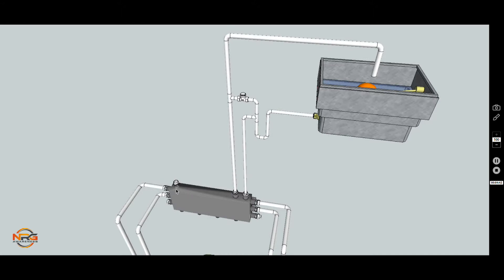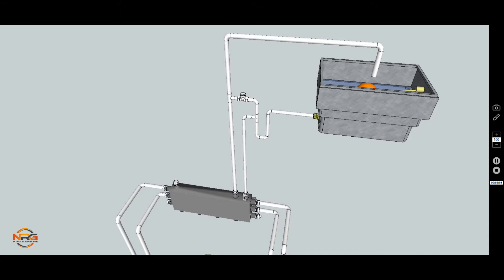The vent situation is that any water traveling in from this side or this side will always collect at this point, and that's exactly where the vent is. So any air will be immediately vented out by the Energy Zone manifold. There's 75mm or less between the vent point and the cold feed fill point, so there's no potential for pumping over. There's no extra pressure here compared to here, so there's very little chance of the water rising up and pumping over the system.